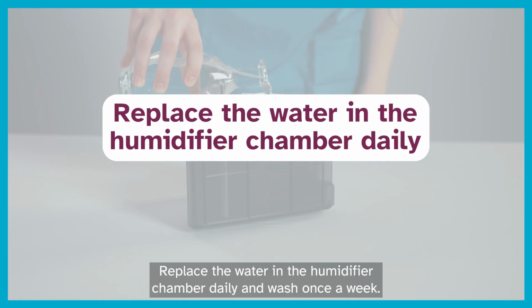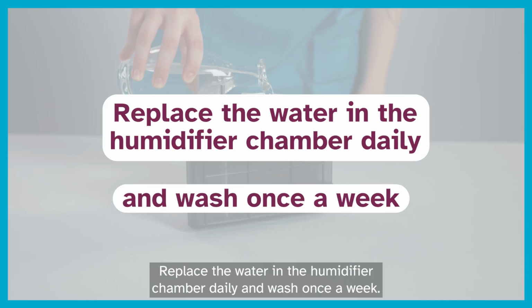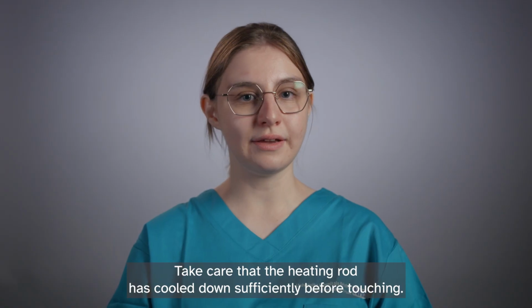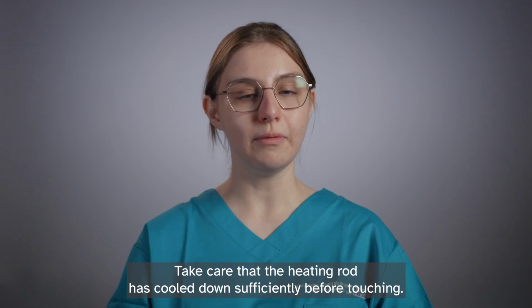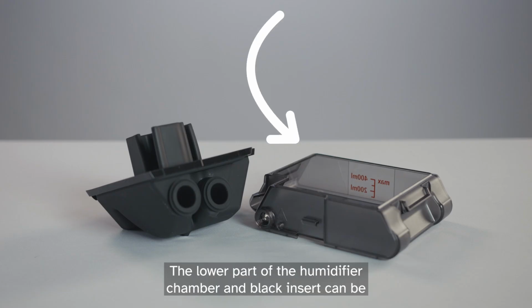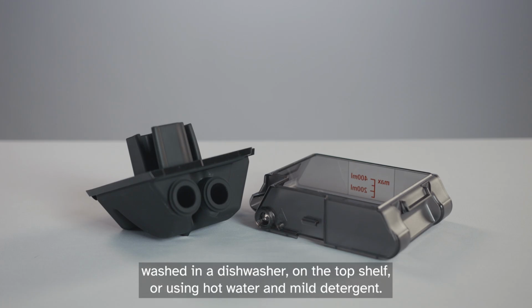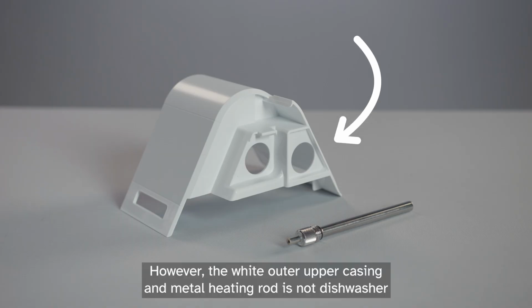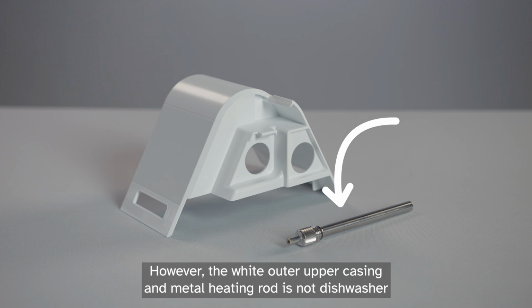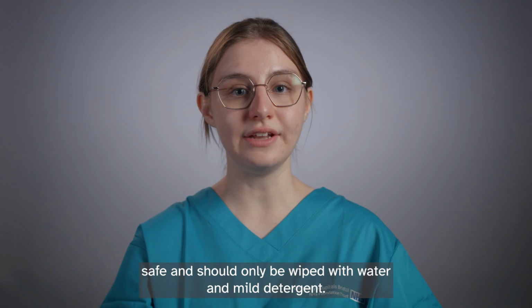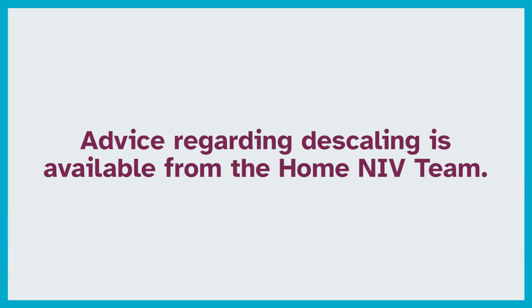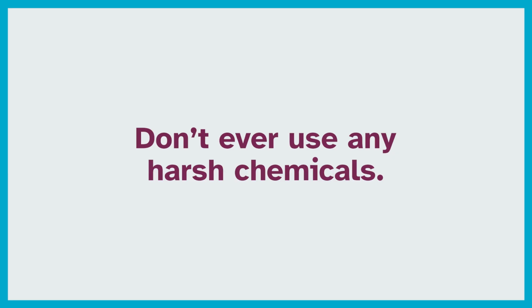Replace the water in the humidifier chamber daily and wash once a week. Take care that the heating rod has cooled down sufficiently before touching. The lower part of the humidifier chamber and black insert can be washed in a dishwasher on the top shelf or using hot water and mild detergent. However, the white outer upper casing and metal heating rod is not dishwasher safe and should only be wiped with water and mild detergent. Advice regarding descaling is available from the Home NIV team. Don't ever use any harsh chemicals.